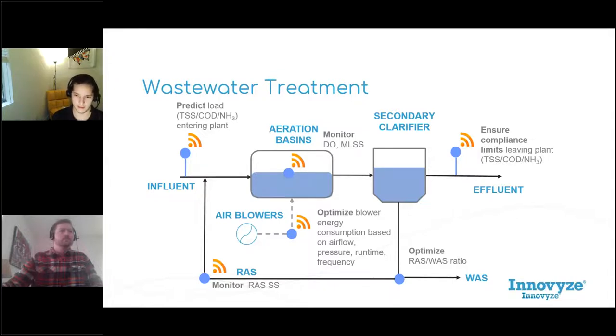By using predictive models or anything of the sort, we can guess that future, look at the actual influent quality, and make a decision based off real-time BOD data or real-time COD data. Based on what the mixed liquor is, we can use some of the oxygen already available in the water and decrease the amount of energy required by planning ahead and looking at the blower level. Hey, where is the optimum energy, optimum operating point for this blower? Same thing we do with pumps. Can we leverage a better operating point, basically, and use that instead of just adjusting it freely until we reach a very specific DO, whether or not the chemistry needs it, right?